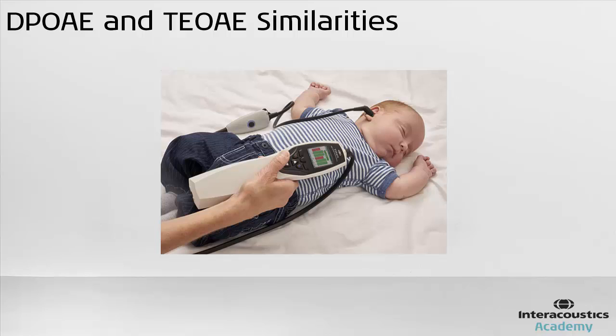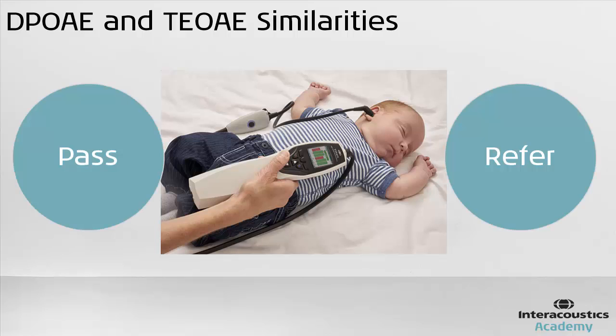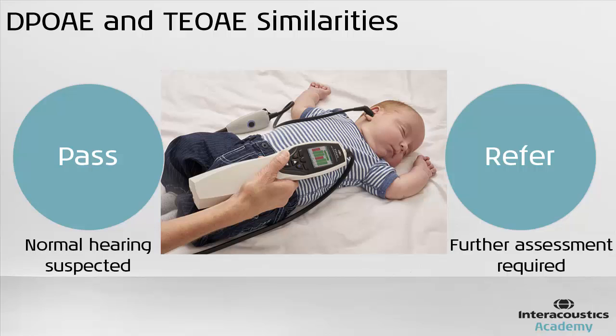In a screening programme, the OAE device will produce either a pass or a refer test result. With a pass, the chance of having a hearing loss that requires immediate intervention is very small. With a refer, not much can be said about the hearing and thus no conclusions can be made — further investigation is needed in these cases.